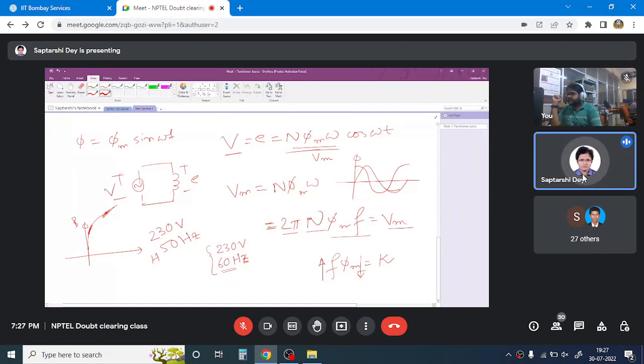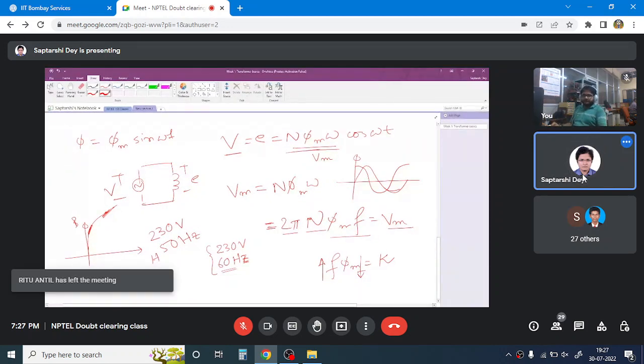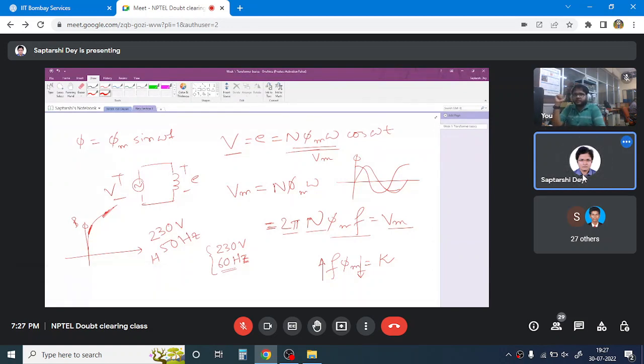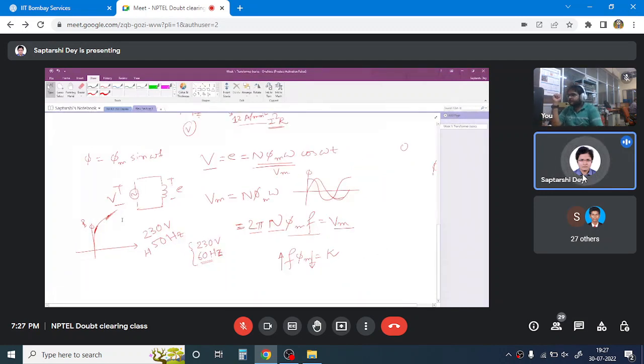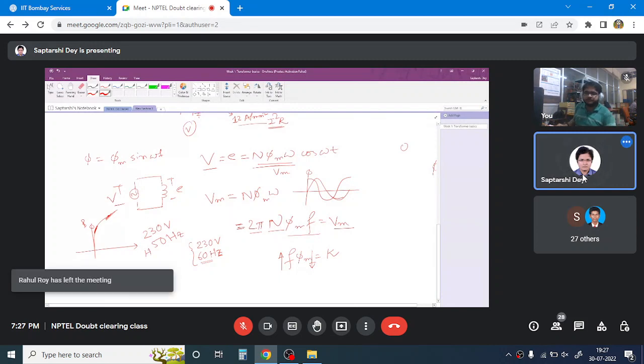In this region, your magnetizing inductance will drop. The transformer will draw a large no-load current. The no-load current itself will be very large, so you might not be able to supply the full load. Might not be able to connect a full load to the transformer. Not only that, this also creates distortion in the no-load current, in the transformer current, in this kind of situation.